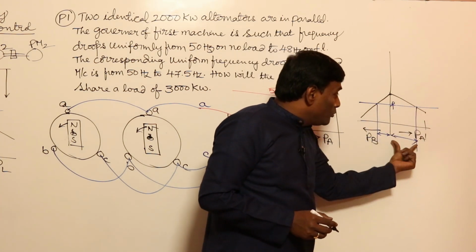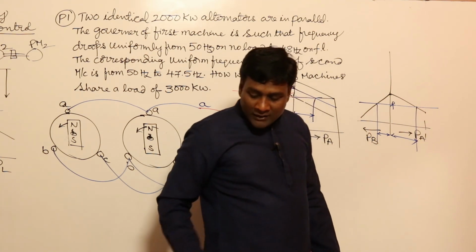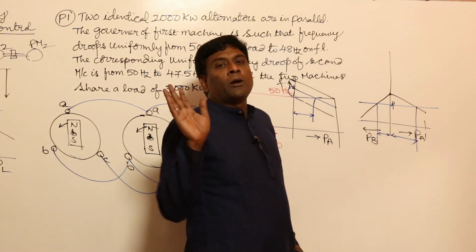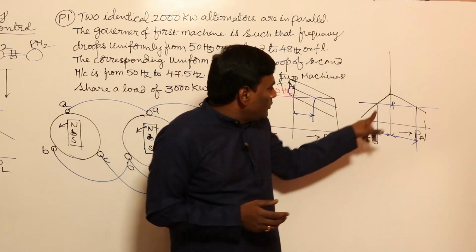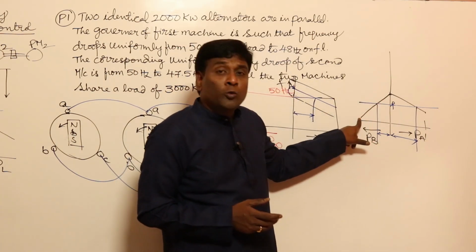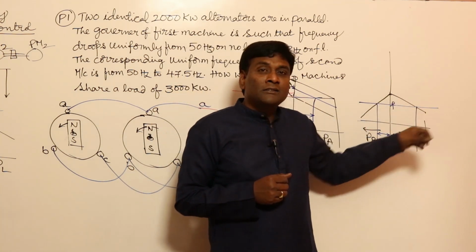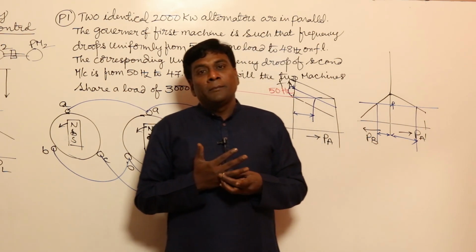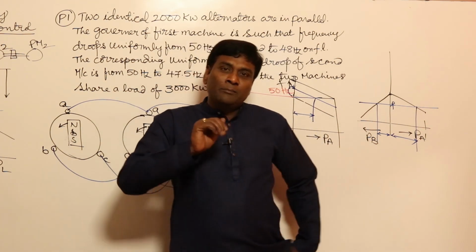That's why it is supplying more power, it is supplying less power. No, no. For example, in the economic load dispatch problem, whatever has more drooping characteristics can be a hydro station, and whatever has less drooping characteristics can be a steam turbine. Then you have to give more preference to hydro as a base load plant.